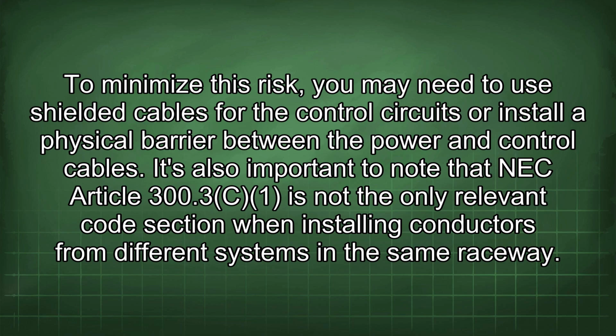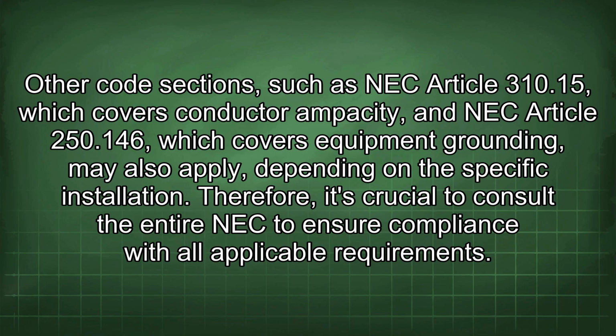It's also important to note that NEC Article 300.3 is not the only relevant code section when installing conductors from different systems in the same raceway. Other code sections, such as NEC Article 310.15, which covers conductor ampacity, and NEC Article 250.146, which covers equipment grounding, may also apply, depending on the specific installation. Therefore, it's crucial to consult the entire NEC to ensure compliance with all applicable requirements.